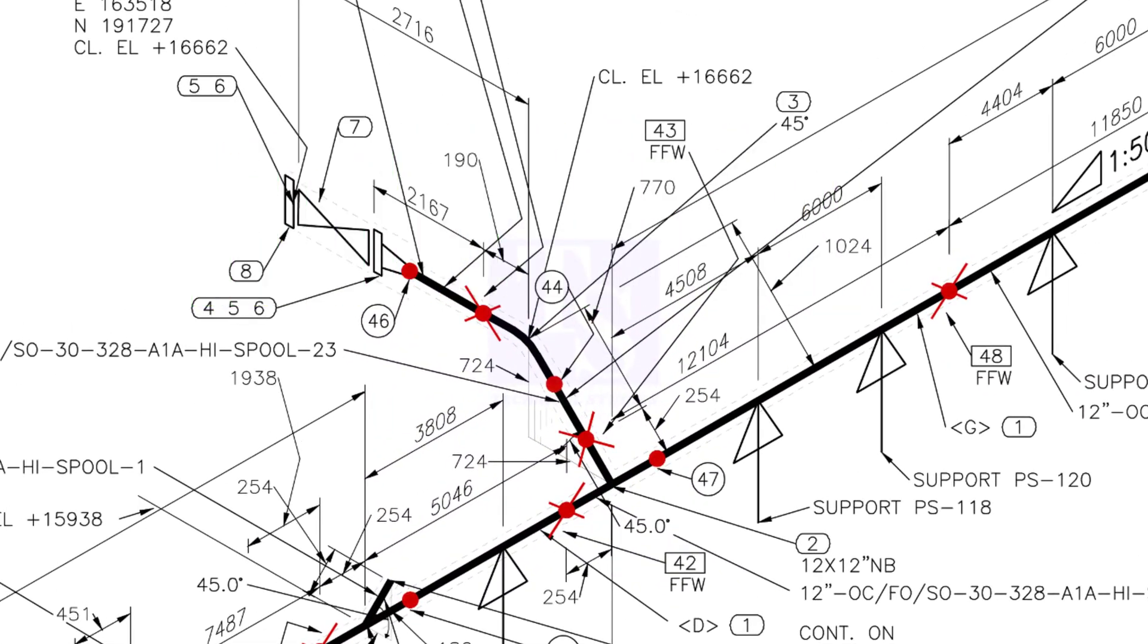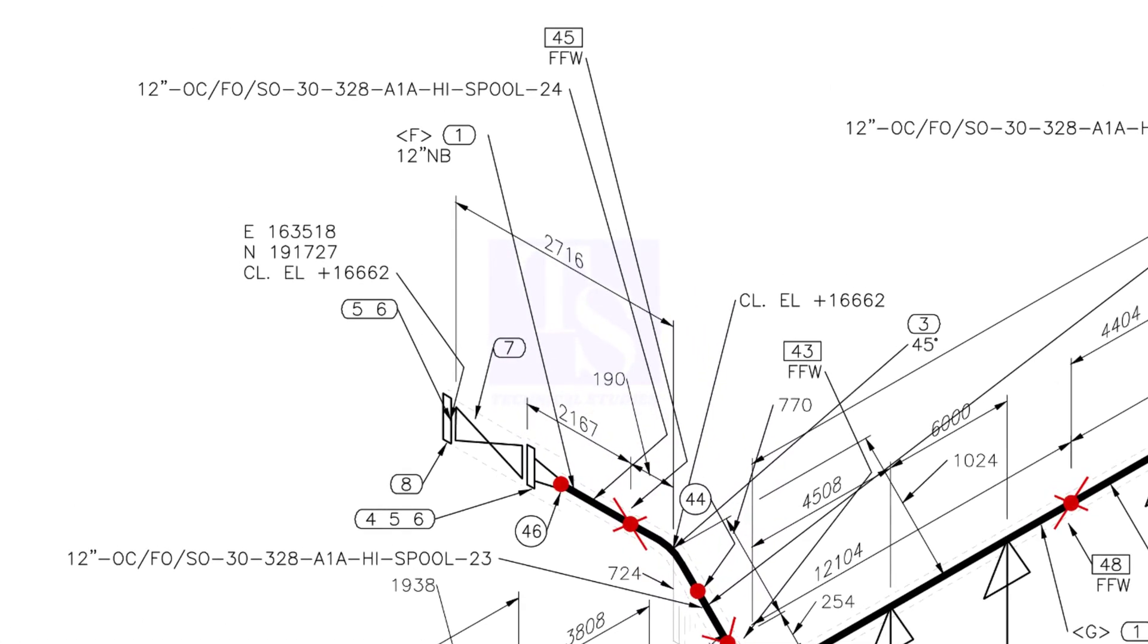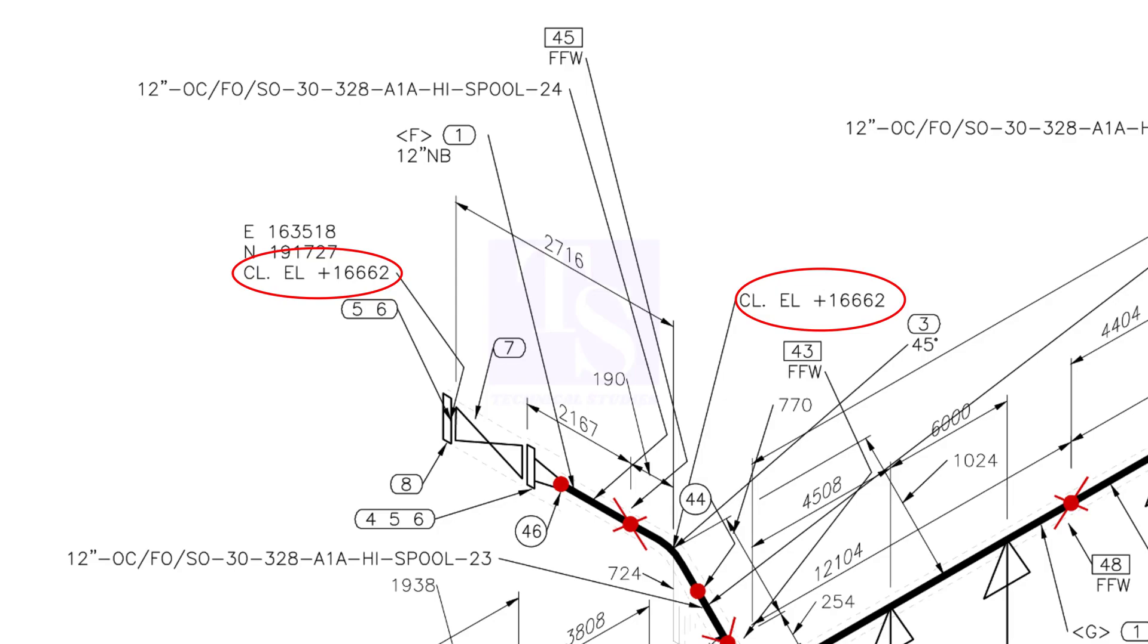Let us check the slope of this spool. The slope symbol is not shown. Let us cross-check the elevations. The center elevation of the spool at the end is 16,662 mm. Center elevation at the other end also is 16,662 mm. What do you understand from this? This part of the piping is not sloped.